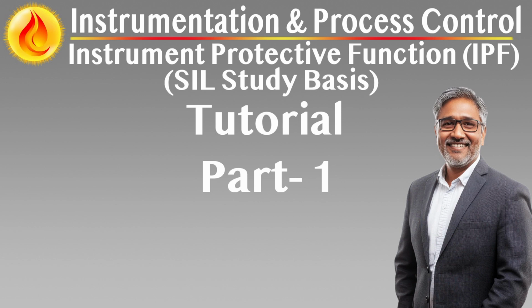Accurate classification of these failure types is essential for estimating the probability of failure on demand, PFDavg, which in turn determines whether the IPF meets its assigned safety integrity level, SIL. All IPF components, sensors, logic solvers, and final elements are subject to failure modes. SIL verification requires quantifying how many of those modes are dangerous, and of those, how many are detectable through diagnostics or proof testing.